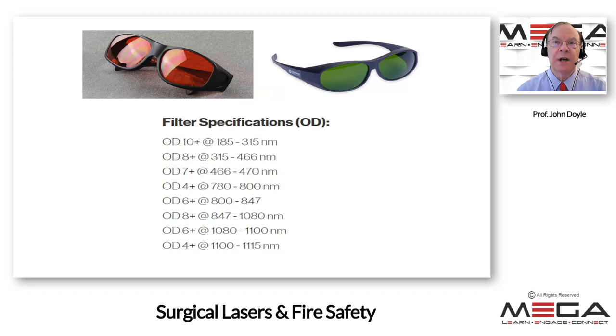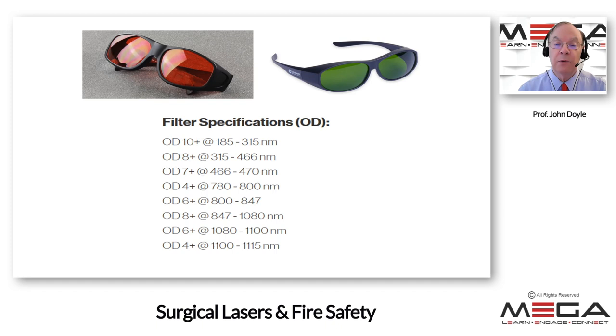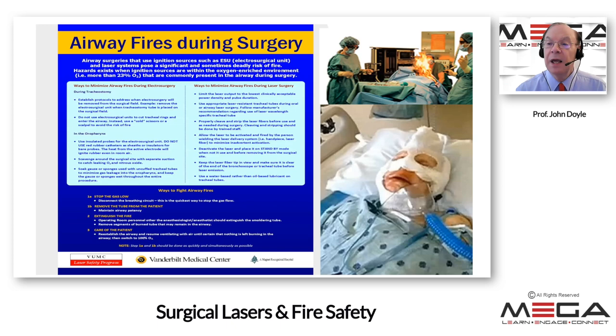You want to use safety goggles or glasses to protect your eyes and the patient's eyes. For patients, we typically cover the eyes with saline-soaked gauze and tape it in place. For operators, glasses that filter out various frequencies are used depending on the laser. For example, an infrared laser may require filtering at 1,100 to 1,115 nanometers, whereas ultraviolet, violet, or red lasers will require lower wavelength protection. The glasses you use will depend on the specific laser being operated.